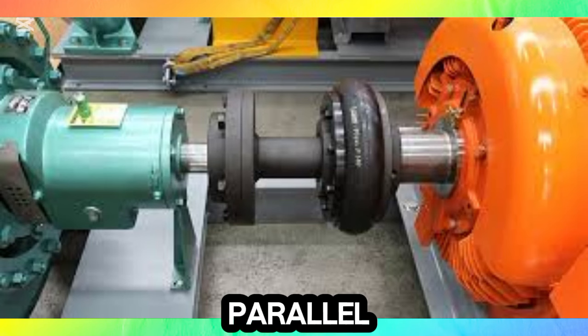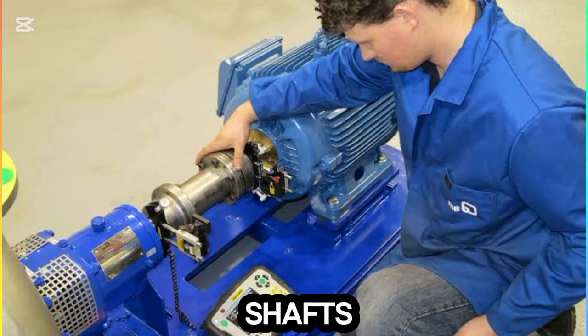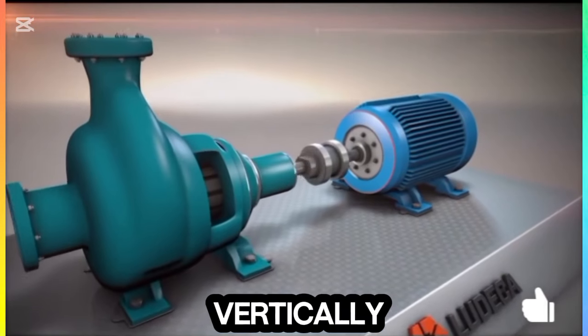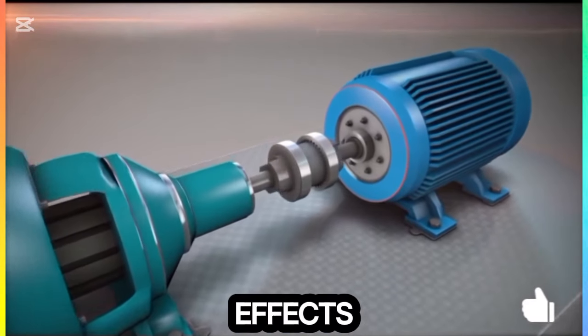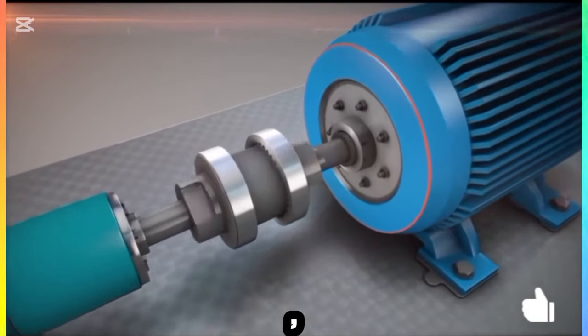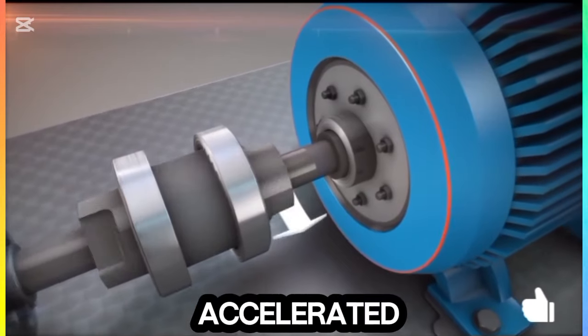2. Parallel offset misalignment. The shafts are parallel but not aligned on the same center line. This results in one shaft being horizontally or vertically displaced from the other. Effects: increased load on couplings, shaft bending, and accelerated wear.